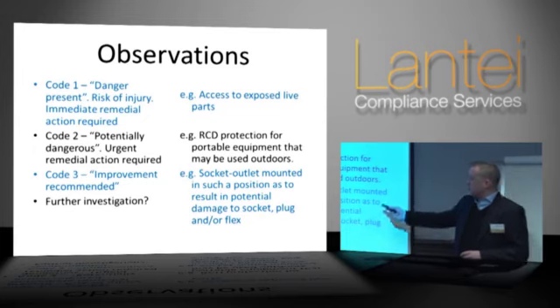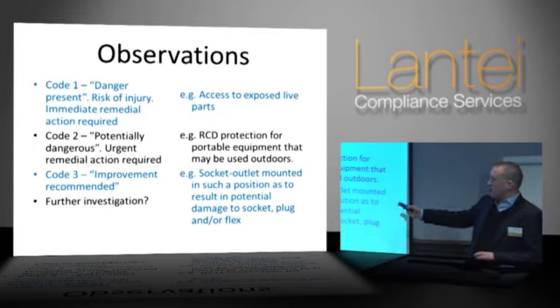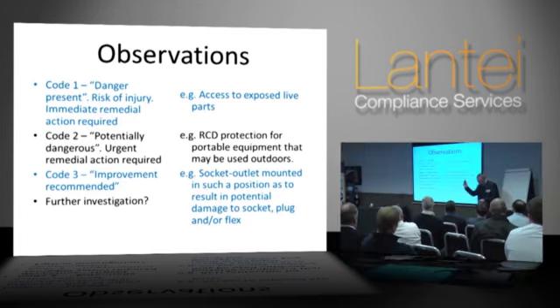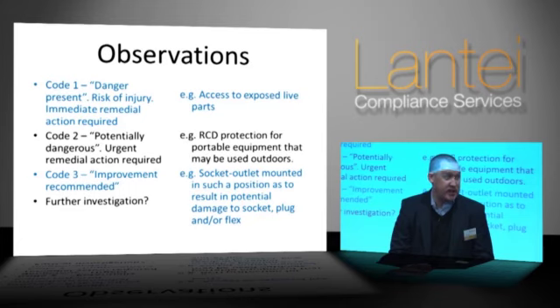Now, we've got 2 examples for the C2 and the C3. The first one on the screen is regarding RCD protection for portable equipment that may be used outdoors. Clearly what we're saying there is, even though this is a relatively new requirement, even if we've got a very old electrical installation, what we're doing in effect is taking electrical equipment outside the equipotential zone, where we haven't got our protective measures fully in place. That's why it wants it to be an RCD.